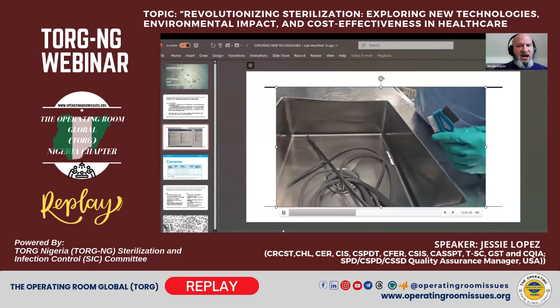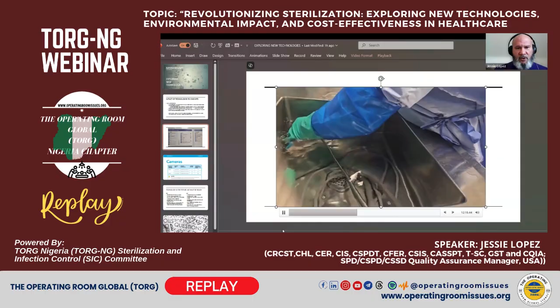When you're utilizing detergents, it is important to understand the properties of the detergent and how difficult or simple it is to rinse off the surface of the device. Some detergents are easier to rinse, while others are a little bit more difficult. We utilize a neutral detergent with enzymatics that can be a little difficult to remove off the surfaces of devices if you do not properly rinse it.